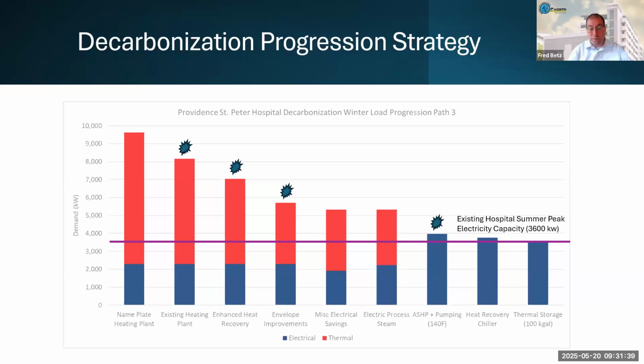Similarly, going from an R3 wall, which is mass concrete, up to even just an R12, it's a 75% reduction. And R12 is not exactly pushing the boundaries here. And so that, again, on the peak conditions, it's taking away yet another megawatt and change of our heating load. So we're working our way down towards that beneficial electrification, but those were the big demand side items.